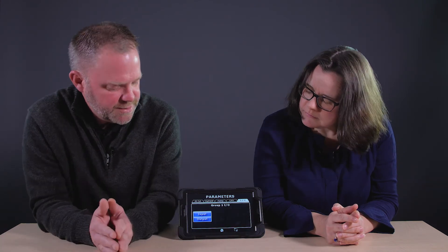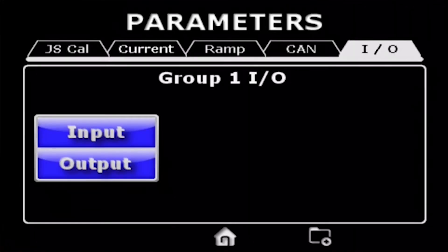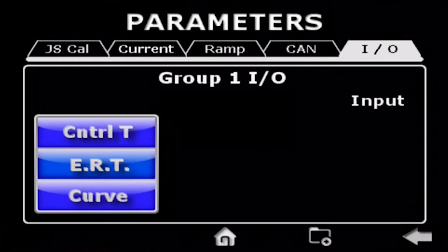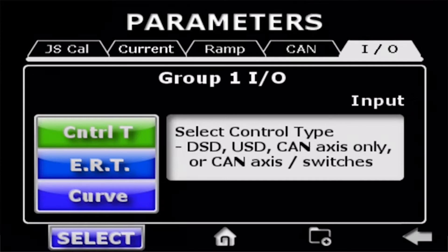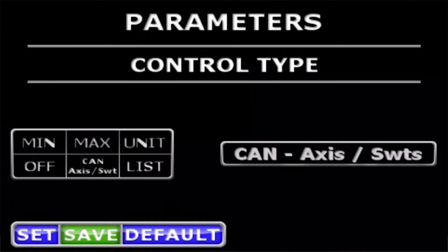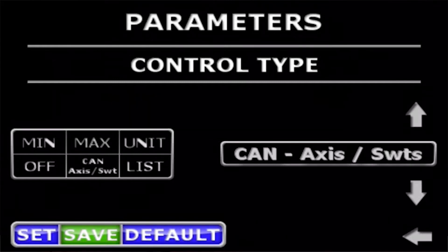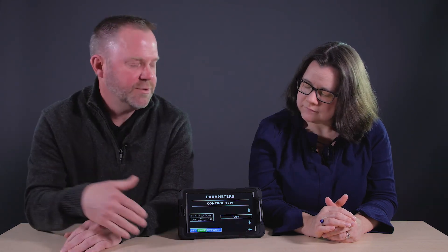On the I/O page we can select our input and output types. On the input we have control type, ERT — which is enable release timer — and an input curve. We'll select control type, and you can see we have CAN axis with switches. In J1939 there's a limited number of switches and locations, so it's very easy for the operator to select where his enable switch might be or what his fine control switch may be. We also have CAN axis only with no switches, USD — unisolenoid driver — for a single solenoid output with a voltage input, dual solenoid driver with a dual solenoid voltage input, or you can turn the group off, in which case that group is blacked out and you're not using it, so there's no need to look at those parameters.